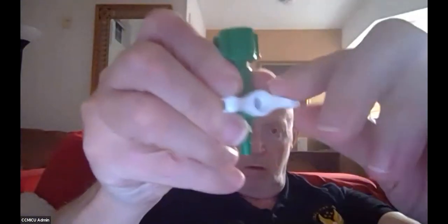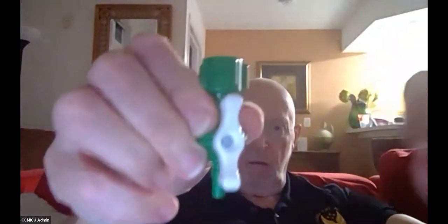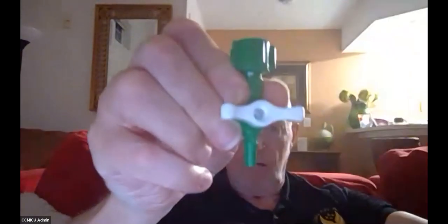So this is completely new. We haven't seen one of these before. At first glimpse, it's kind of a strange fitting, right? It's got a DISS connector on this end, so this is a DISS thread. And this is a short, squatty Christmas tree. It also has a quarter-turn on/off valve. And just so you know, that's on, that's off, all right?